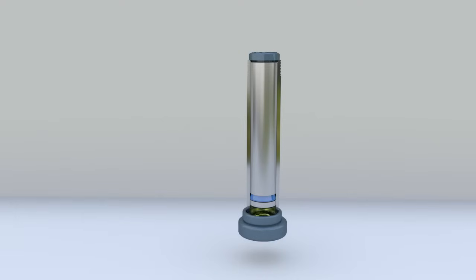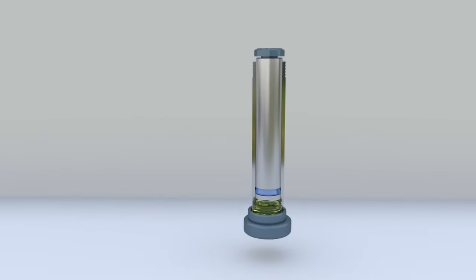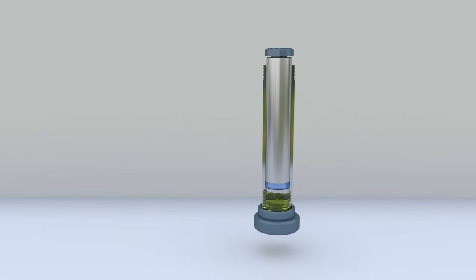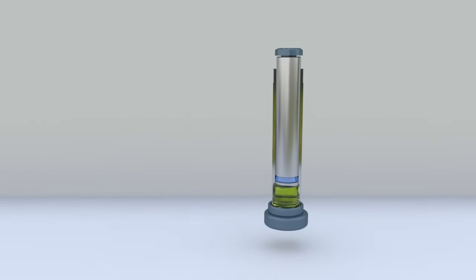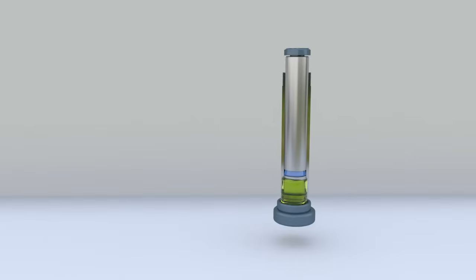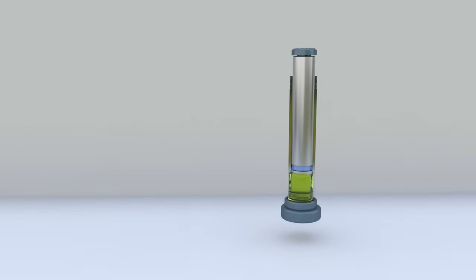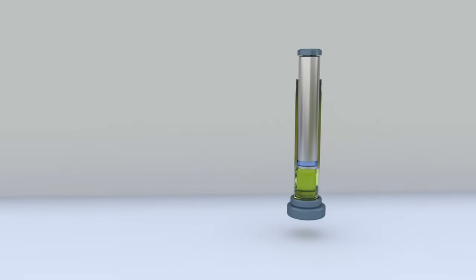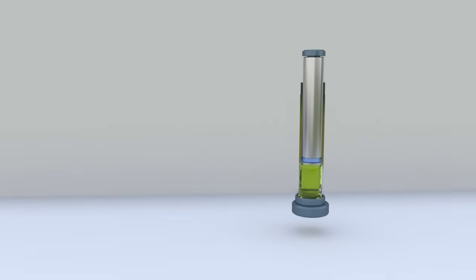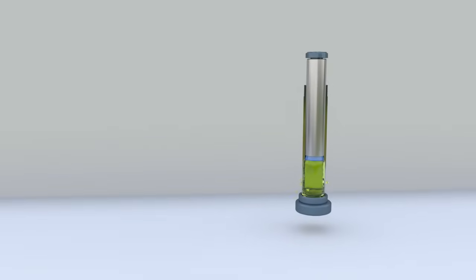In single-acting hydraulic cylinders, the liquid can only act on one side of the piston. The piston rod can be retracted by the weight of the load or by spring pressure. An example of a single-acting hydraulic cylinder is a jack cylinder.